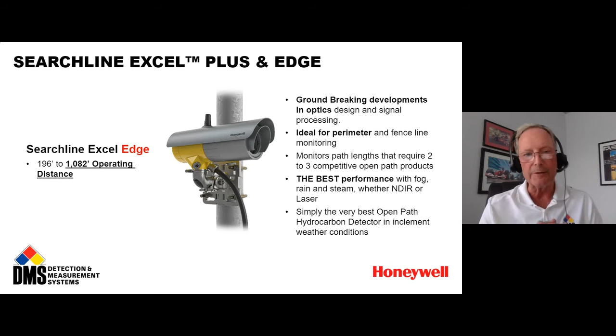Because there are two limitations of an open path hydrocarbon gas detector. One is that when it sees gas, it can't tell you where the gas is within the beam because it's just counting hydrocarbon molecules from one end of the beam to the other end of the beam. The other limitation is that if fog gets dense enough, you run the risk of the fog blocking the IR beam from making its way to the receiver at the other end. So if you can make a quantum leap in the performance of the optics to cut through that fog, that becomes a very big deal. And that's exactly what's happened here. That's why this product has just jumped way ahead of everything else on the market in dealing with fog, steam, and rain. So it quite literally is the best open path hydrocarbon detector on the market for dealing with inclement weather conditions, which for customers along the Gulf Coast is of particular concern.